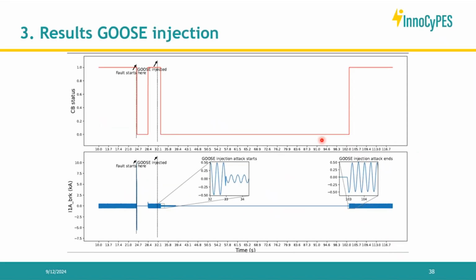Here is the example of how we did the goose injection. It's the same thing: here you see where the fault starts, where the goose is injected, and how the system perturbates. By injected, I mean we replay a scenario where the system is supposed to be running normally, but a malicious actor wanted to send a packet saying there's a fault.